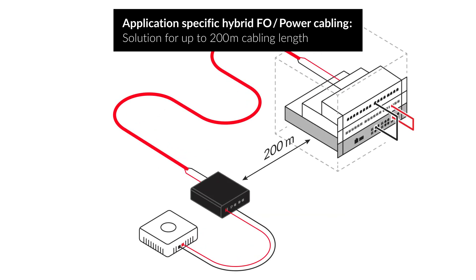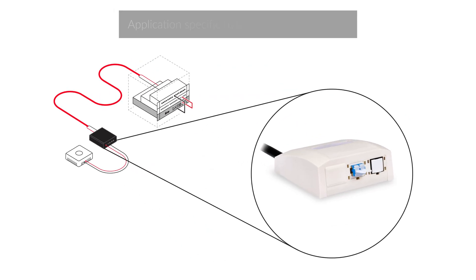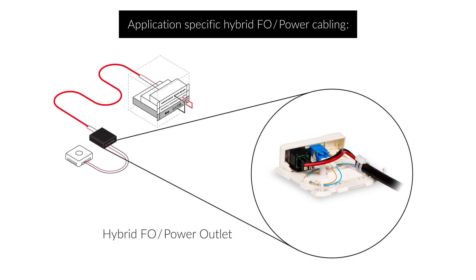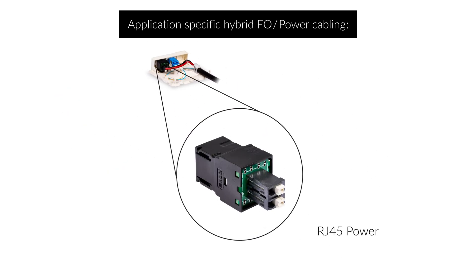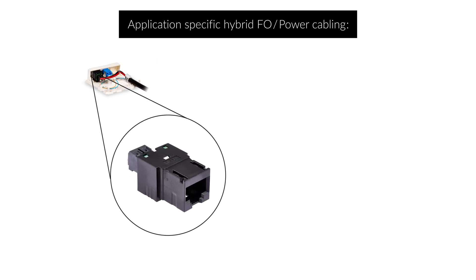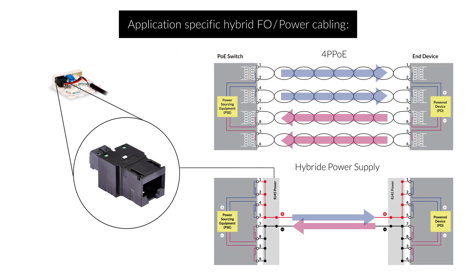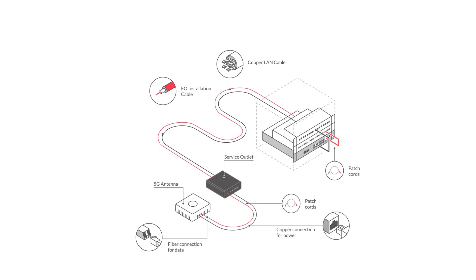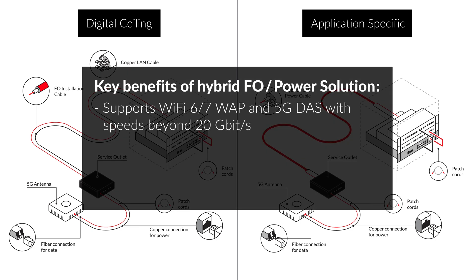Permanent links of up to 200 meters length can be supported with this cable. Since RJ45 connections cannot support any meaningful data rate over 200 meters distance, no extra RJ45 data port is needed. However, the hybrid outlet should support some fiber management. The RJ45 power module from R&M provides a spring clamp termination for two wires up to AWG-16 and splits the supply voltage to the RJ45 pins according to 4P PoE requirements. Whether as part of the digital ceiling or as application-specific cabling, the R&M hybrid fiber optic power solution offers unique benefits in terms of higher data rates, longer transmission distances, flexibility and modularity, and reliable PowerSafe RJ45 connectivity.